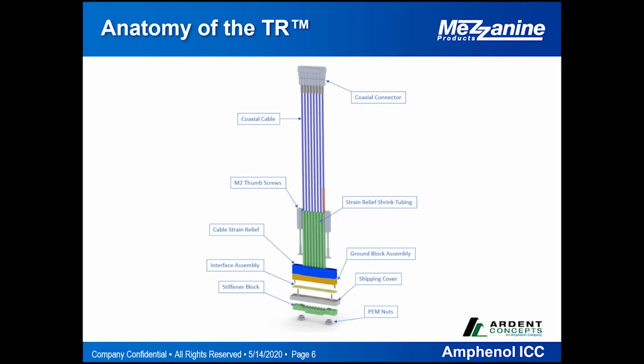We offer a standard coaxial cable, an 047 diameter flexible cable, which allows room temperature escape of multiple signals out to the instrumentation on the room temperature side of a dilution refrigerator and a cryogenic or quantum system. Those cables are then ganged into a block assembly, and the proprietary contact sets live in our interface assembly, which we'll look at in the next slide.